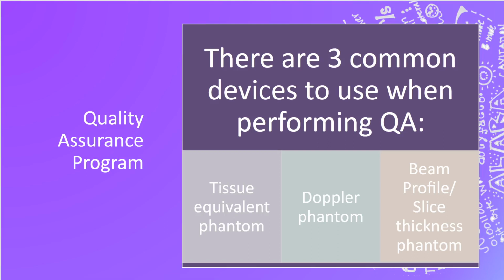Now, when we are looking at our machine, I had mentioned that we want to recreate the same environment for every quality assurance check that we are doing. And we can check the machine components by using what we call phantoms. The 3 most common phantoms that we use are a tissue equivalent phantom, a Doppler phantom, and a beam profile phantom, also known as a slice thickness phantom.